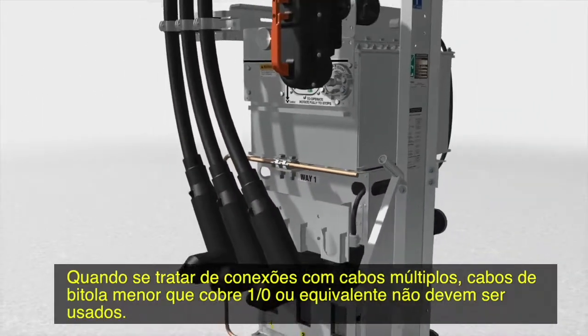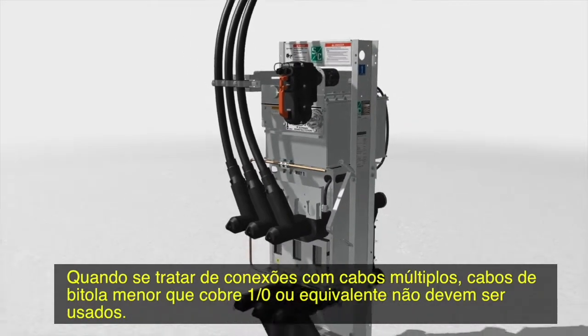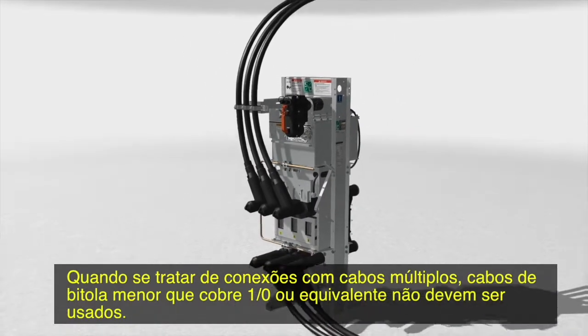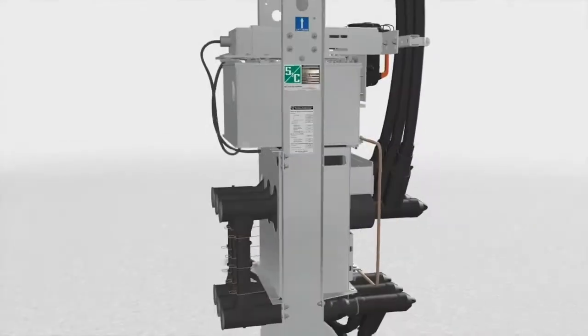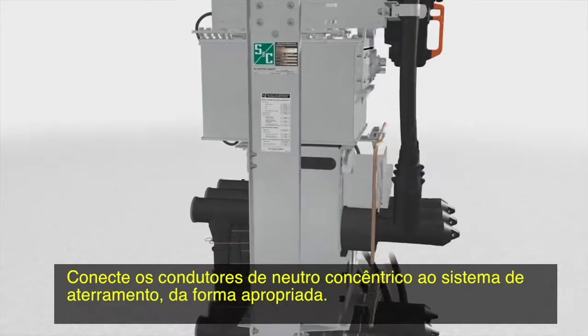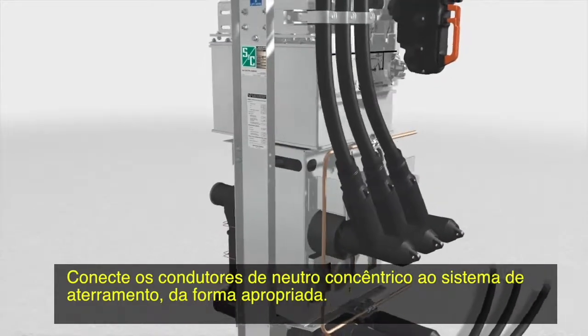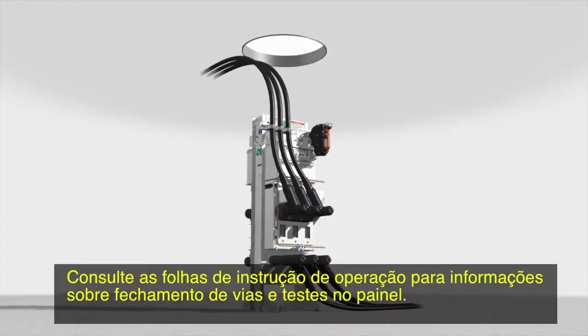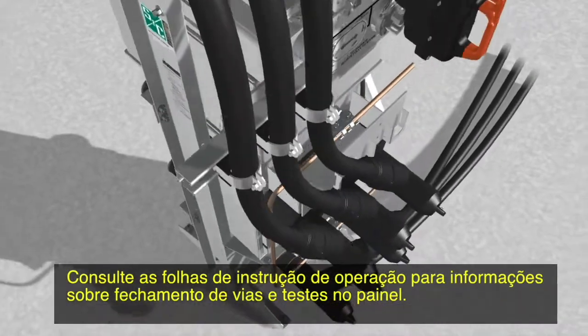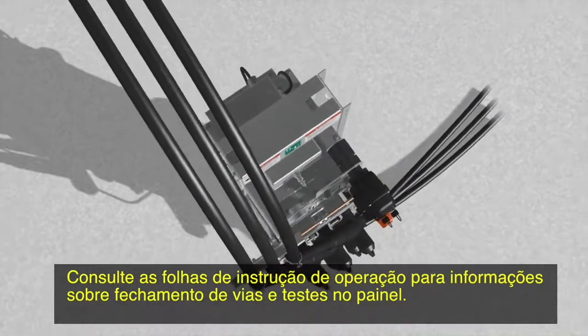For a multiple cable connection, cables smaller than 1/0 copper or equivalent should not be used. Connect the cable concentric neutral wires to the grounding system as appropriate. Refer to the operating instruction sheet for information on closing the ways and testing the switchgear.